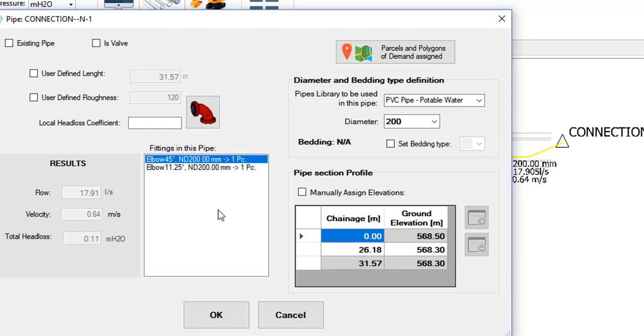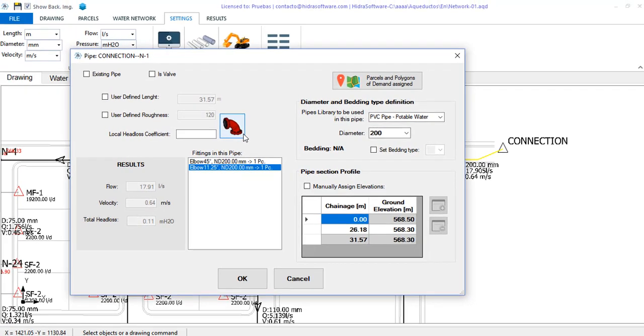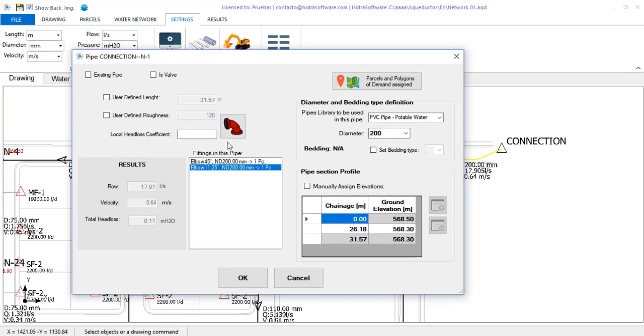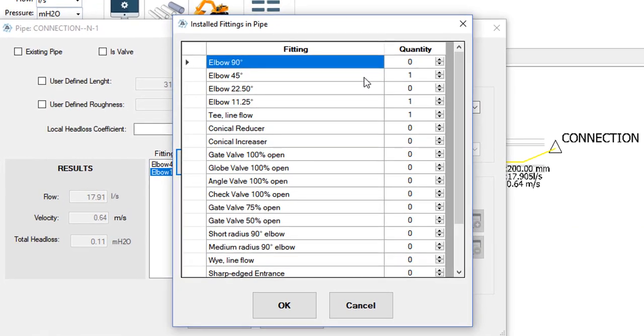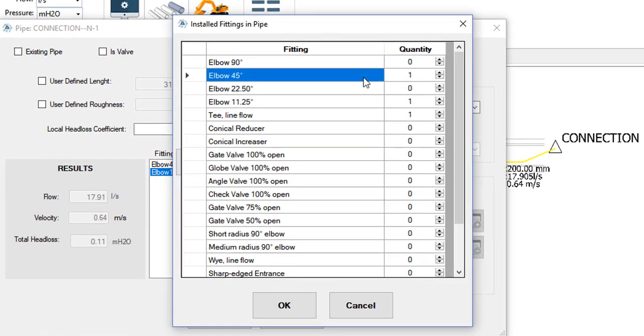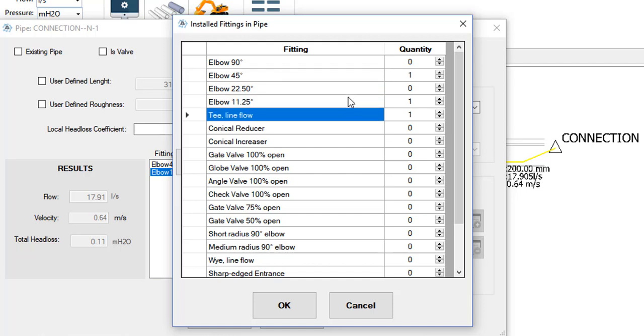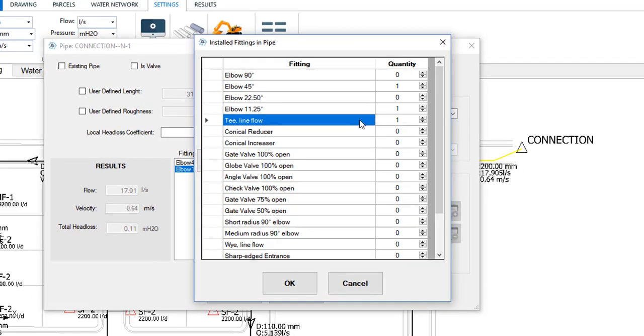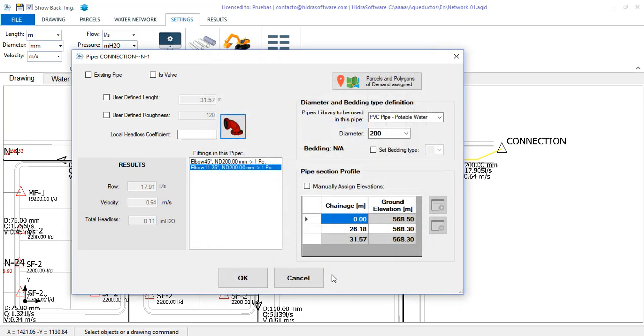Now, depending on the selected method, if you go to the list of fittings assigned to this section by clicking this button, you will see that the software has automatically included the corresponding elbow from the parts list with localized head loss coefficient. And, additionally, it has added the respective T at its end downstream. Both pieces will be used to determine the local head loss coefficient to be assigned in the head loss calculation in this pipe section.